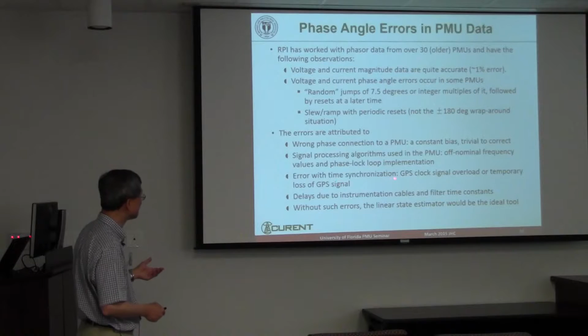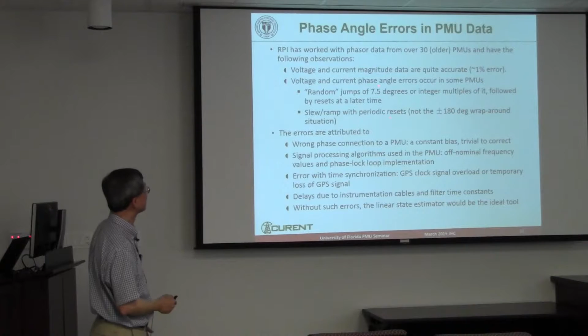Further on, you also get issues like wrong phase connections causing bias, synchronization error, and even instrumentation cable problems—sometimes the CT is far away, and a long cable or the filtering algorithm introduces a bit of delay.